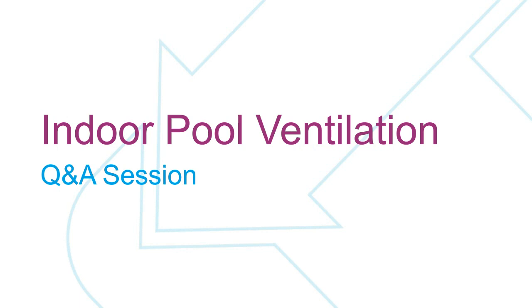I would say that you probably want to... it's hard to monitor with a building automation system is the short answer. Really, the best thing right now is the smell. Are you smelling chloramines or are you not? There are some people promoting the use of a VOC sensor for that purpose. Unfortunately, chloramines are not VOCs, so I find that to be a little bit frightening. It may turn out in time that that can be okay, but you're trying to measure something with a sensor that isn't intended to measure that.